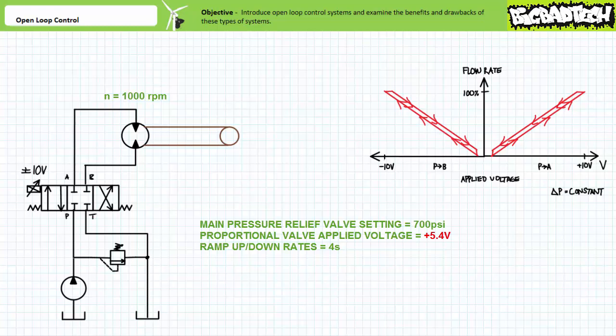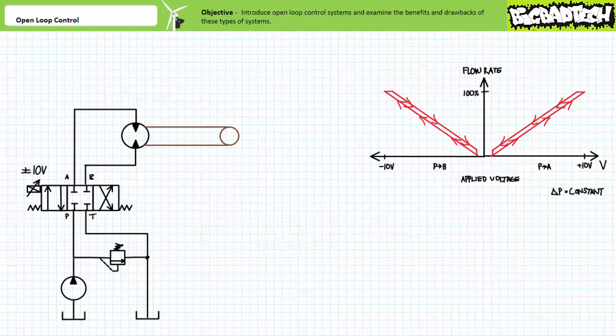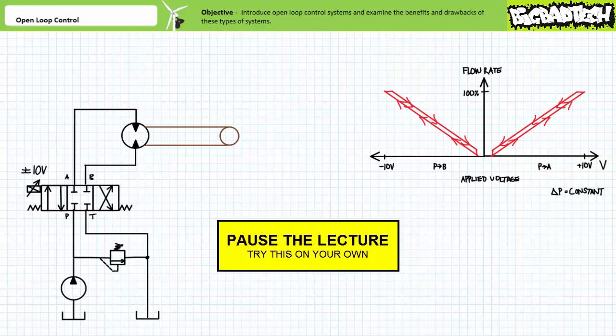When the conveyor belt is started again, this time ramping applied voltage up to only 5.4 volts over the course of four seconds — will the hydraulic motor rotational speed stabilize at the desired 1000 RPM? If not, why? Keep in mind, in this simple example, absolutely nothing has changed: no change in pressure, flow, temperature, friction, or any other external factor. Here's what might occur: when applied voltage is ramped up to 5.4 volts over the course of four seconds, the conveyor belt again undergoes a controlled acceleration.